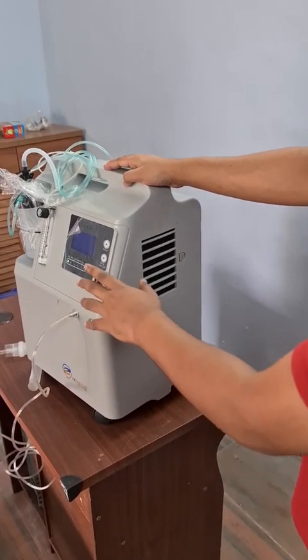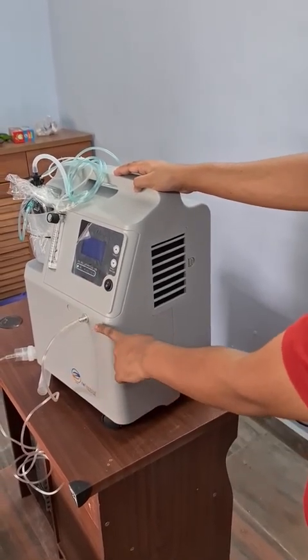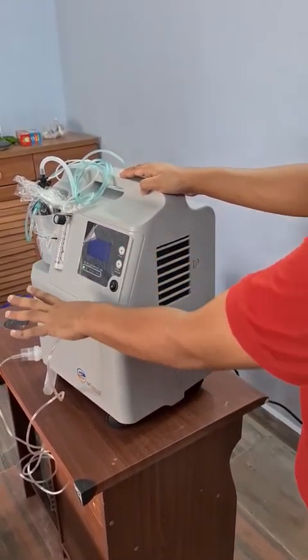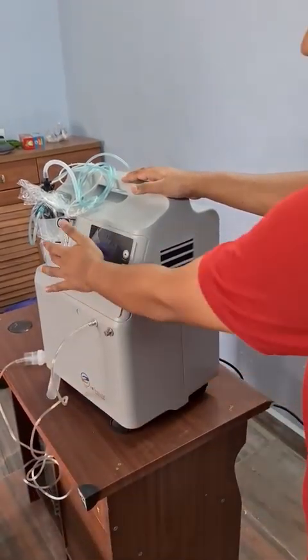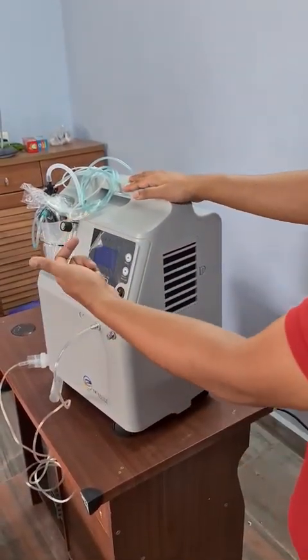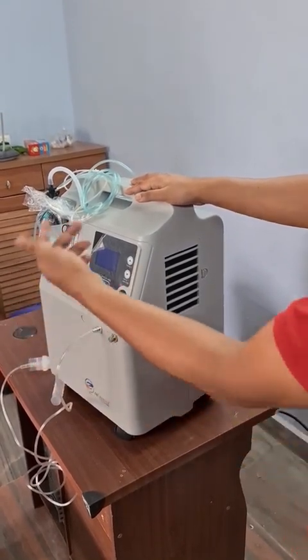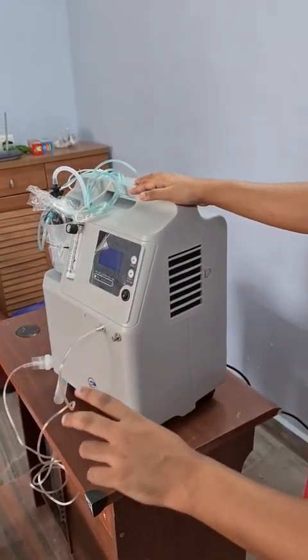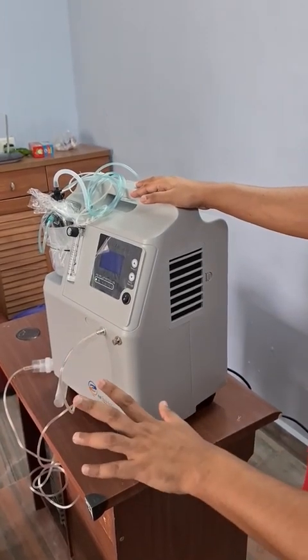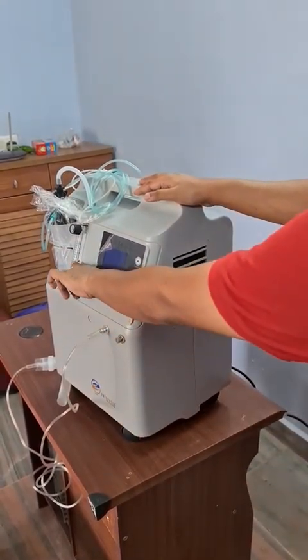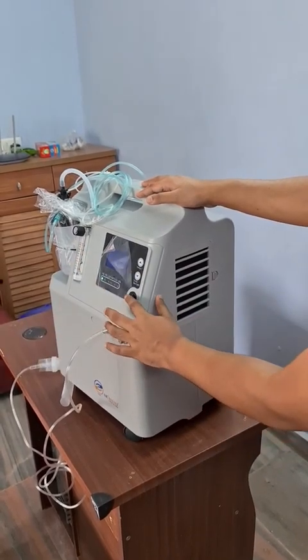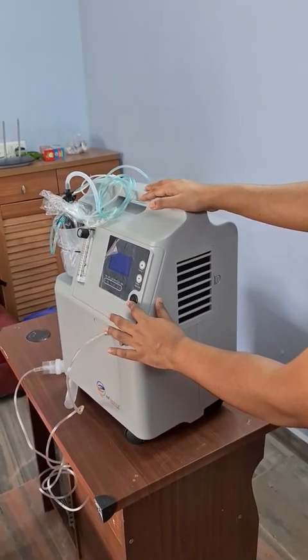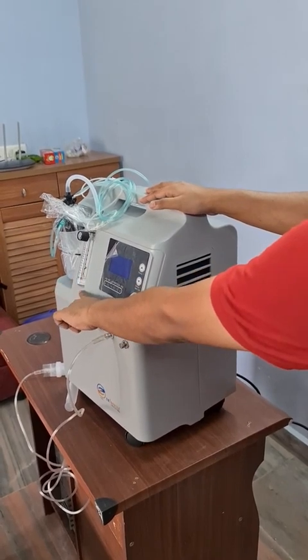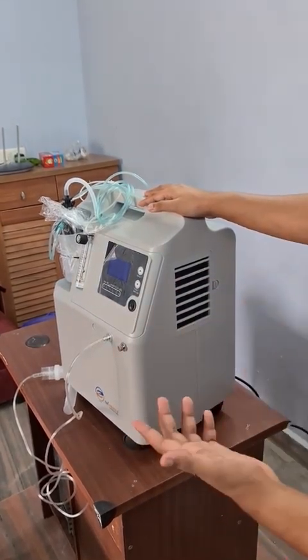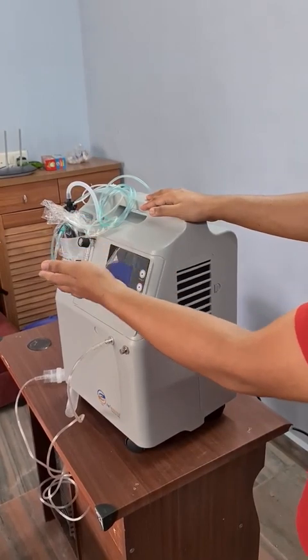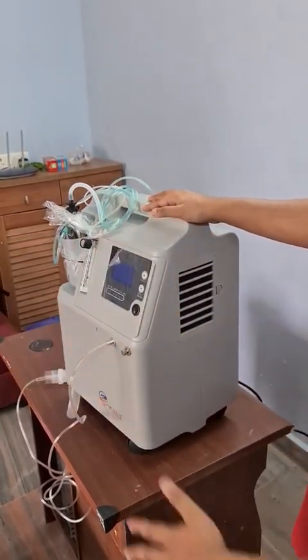So first thing you have to do is switch off the device. I've kept the nebulization port to 0 and oxygen flow rate at 2. Very well, you can switch off the device when the oxygen flow rate is set, because when you again switch on, it will go back to the same level which you have kept it. So there's no need to adjust the flow rate each and every time. Say for example, my flow rate required is 2. I set the knob at 2. Straight away I can go and switch off the device. After some period of time, that ball will come down to 0, and when I want to switch on the machine again, automatically the ball will rise to 2, indicating that the output flow is 2 liters per minute.